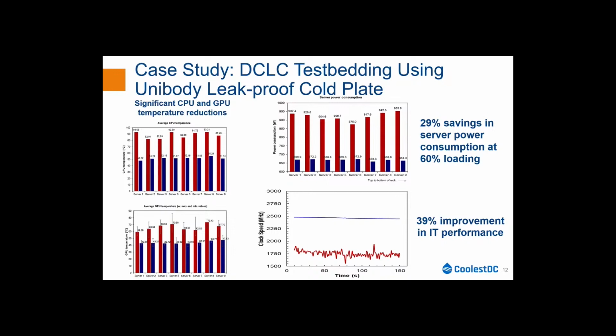That's shown on the right-hand side. The top right corner shows the server power consumption. We're able to slash the server power consumption by as much as 30%, which is very substantial. A 1U server regularly consumes 1.1 kilowatt, but once I switch from air-cooled to liquid-cooled cold plates, I'm able to drop it from 1.1 to about 750 watts, so that's easily a 300 plus watts reduction in server power.